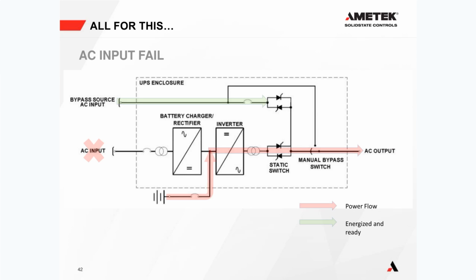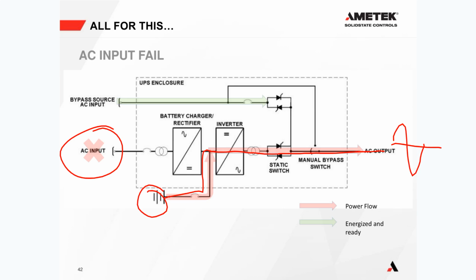So if we put it all together, all we're doing is, remember, we don't want batteries that we have to replace like AAAs and AAs. So all we're doing is we need this DC here to be charged when it's not in operation. And then when the AC input does fail, when grid power does go down, the battery just continues to feed the inverter, and we have this beautiful AC waveform on the output as if nothing happened. It's just like pulling the plug out of your laptop. The screen stays on, all the information is saved. The battery just continues to supply power to the inverter.